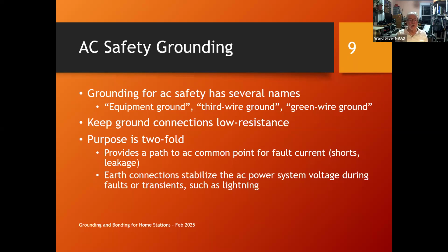The whole purpose is to connect whatever it is all the way back to your AC service panel reference point. Ground connections in AC, to be effective at AC, need to be low resistance. Their function is to carry all of the possible fault current in a branch circuit until the protective devices remove power from a circuit, whether that's a fuse or a circuit breaker. You want the ground wire to carry all of the fault current, if you've got a short circuit or whatever, until the circuit breaker pops. The whole point is to remove power from the circuit and not have a fire start. So what's important there is not necessarily the inductance, because we're talking about 60 hertz. The important thing is resistance. You want the ground wire to be as big or bigger than the conductors that supply power to your station.